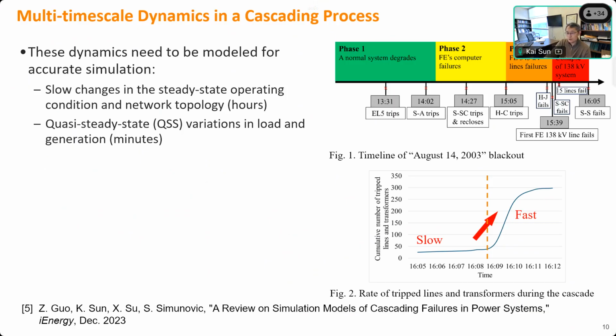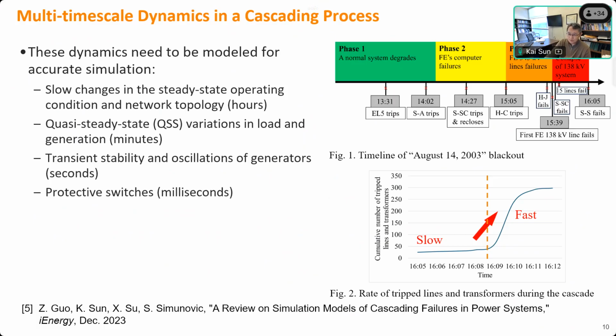Such time scale could be in minutes. If something happens, there will be a transient dynamic and the generator may lose stability, so you need to consider transient stability and even oscillation of generators. Such dynamics will be in the time scale of electromechanical dynamics, usually in seconds. Protective switches may happen in milliseconds, and electromagnetic transient dynamics could be even faster.